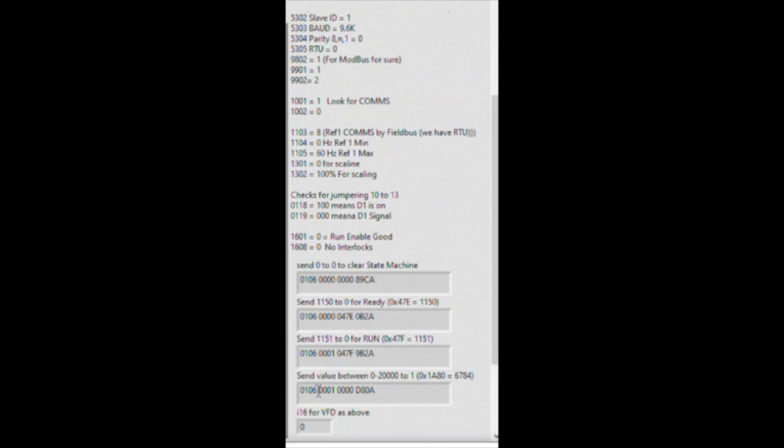This is for the ACS 510, 550, ABB VFD. Here are the settings. These settings are available through the front panel and these are the most important ones. The thing will not work until you get these set. So 5302, pause the video and copy all these down. Some of them need to be set in local and remote and make sure they exist in remote so that the thing will work. You have to power off and power on in order for it to work.